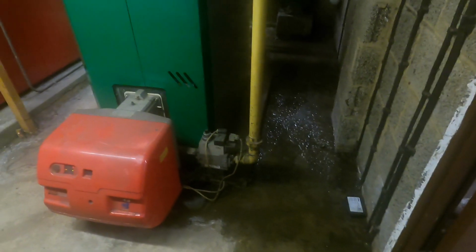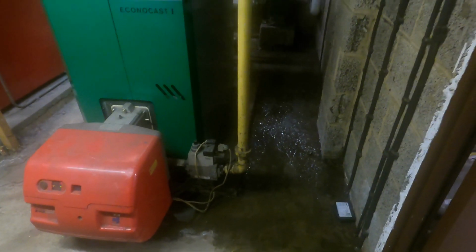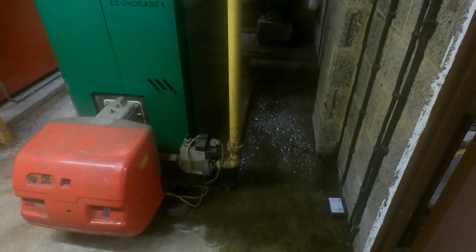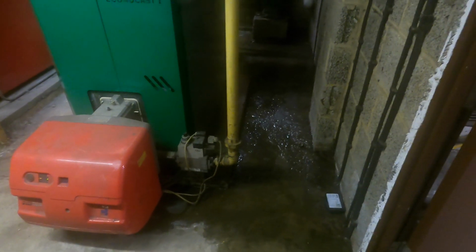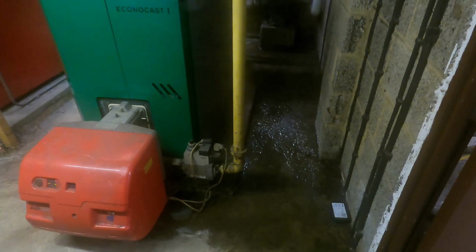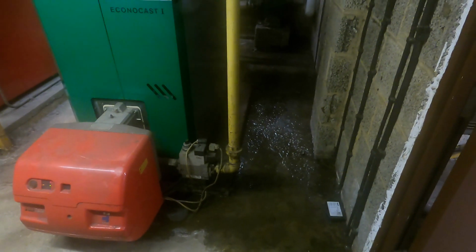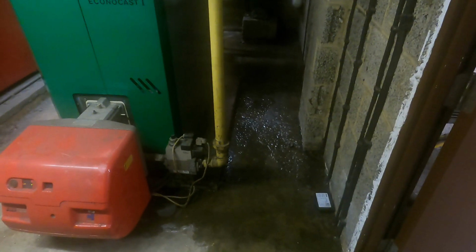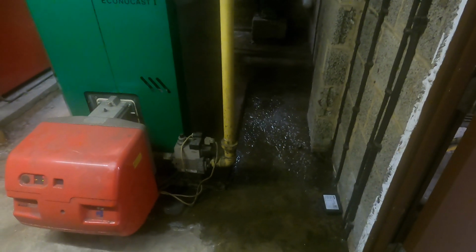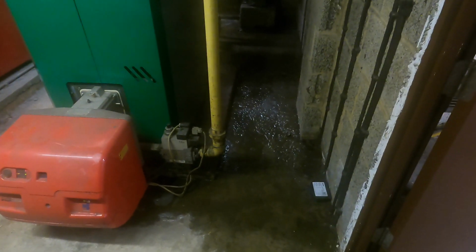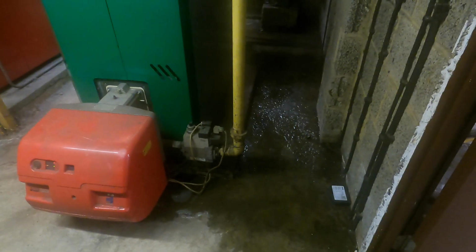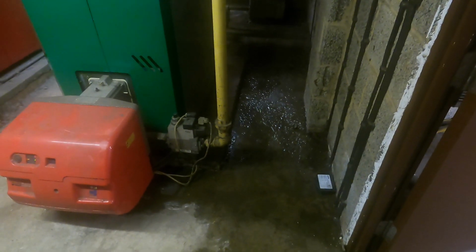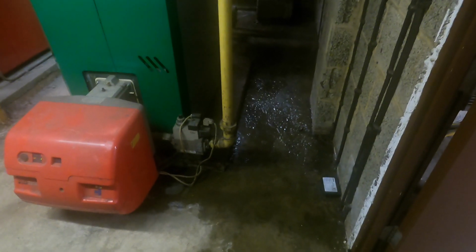The maintenance manager hasn't had the opportunity to really chase this, but now he understands the full extent of the cost of this. So we talk about the 3 levels of cost. We're paying to use the water, we're paying to put that water back down the sewer, and we're actually paying to heat the water. And in some cases this could be a hard water area, and we could be paying to treat the water as well. So there's 4 elements to the cost here.